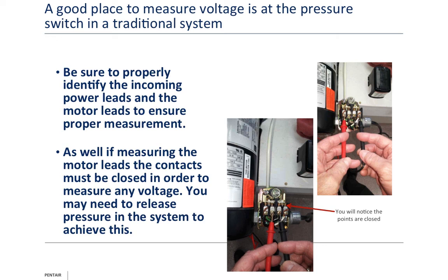Now, I'm going to pause for a second and ask: what's wrong with these pictures? Even our seasoned pro there, my senior trainer at the time, Bill, he's using both hands. He's not using alligator clips or little J-hook clips. And in doing that, if for some reason those probe sets were damaged, and if you notice in one picture his four fingers were touching, he could hurt himself. So always be precautious. If you're going to use two hands, then wear insulated gloves.